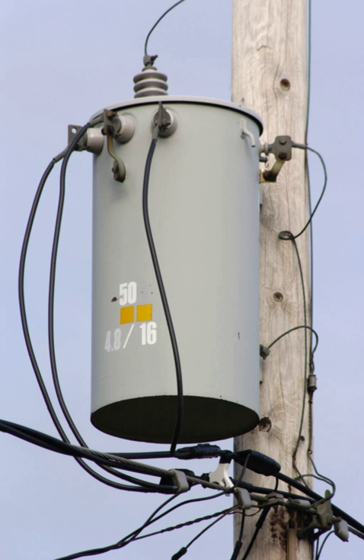Topic: distribution overview. The transition from transmission to distribution happens in a power substation, which has the following functions: circuit breakers and switches enable the substation to be disconnected from the transmission grid or for distribution lines to be disconnected. Transformers step down transmission voltages, 35 kV or more, down to primary distribution voltages. These are medium voltage circuits, usually 600 to 35,000 volts.